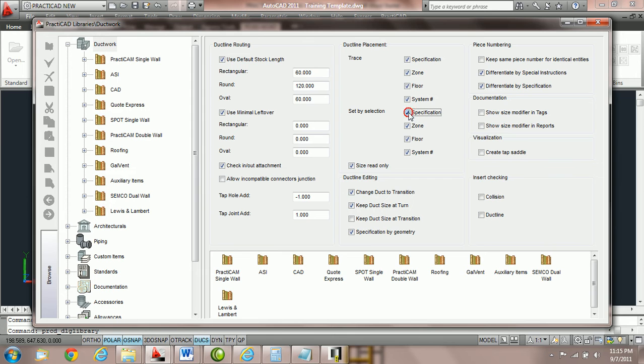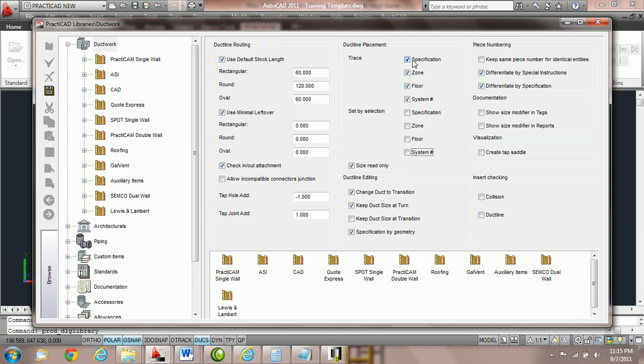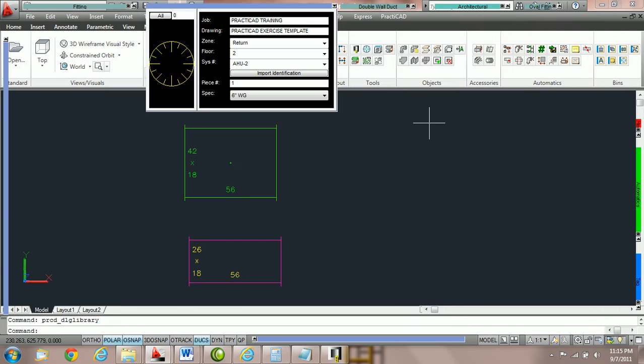What I'm going to do is uncheck the set by selection and we're going to focus on the trace parameters. If these are checked, what PractiCAD is going to do is when I attach a piece of duct to an existing duct line, it's going to make the duct I am holding match the specification, the zone, the floor, and the system number properties. So here I'm going to hit the save key and we're going to exit out of the library.